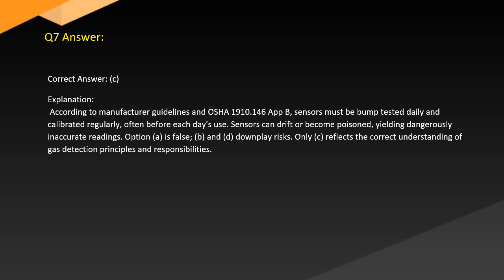Answer. Correct answer. C. Explanation. According to manufacturer guidelines and OSHA 1910.146 App B, sensors must be bump tested daily and calibrated regularly, often before each day's use. Sensors can drift or become poisoned, yielding dangerously inaccurate readings. Option A is false. B and D downplay risks. Only C reflects the correct understanding of gas detection principles and responsibilities.